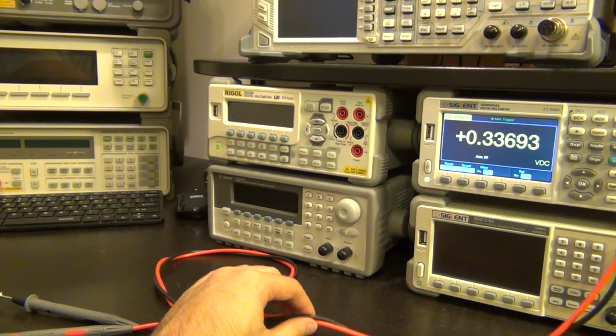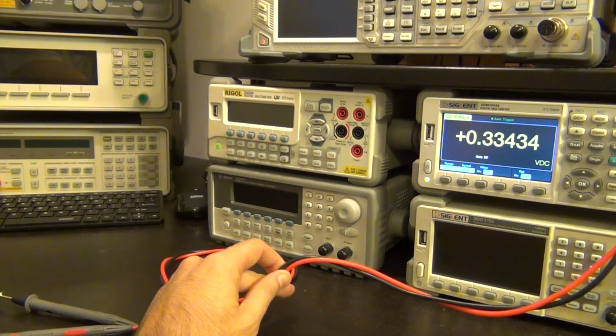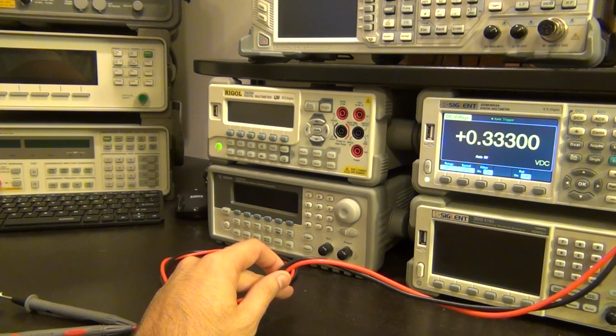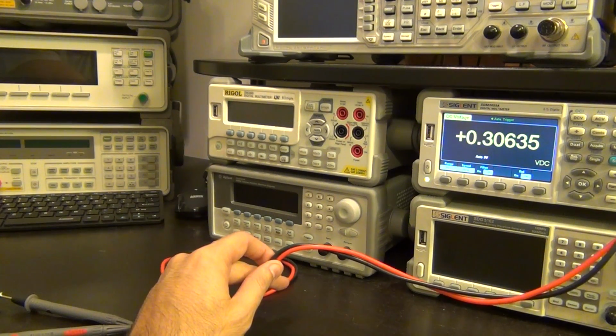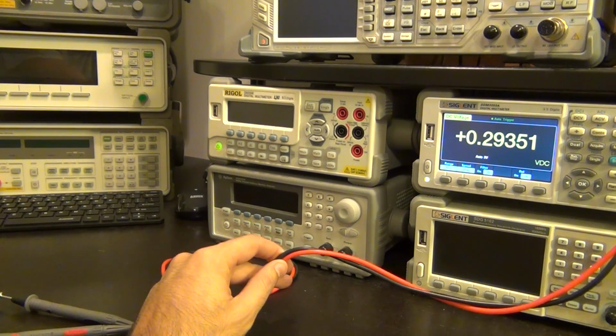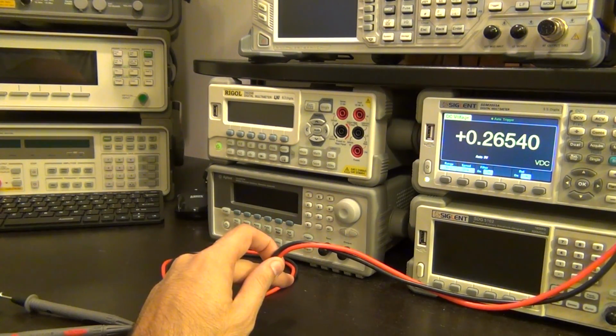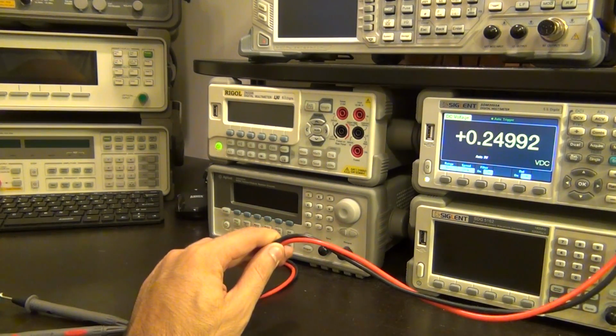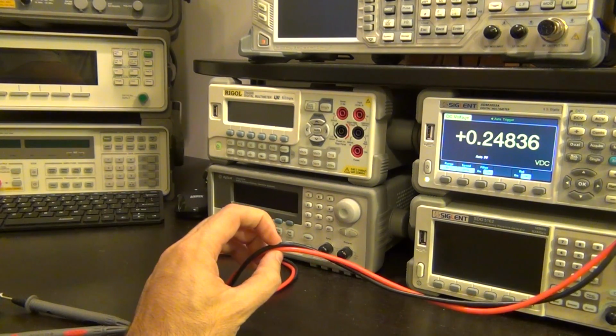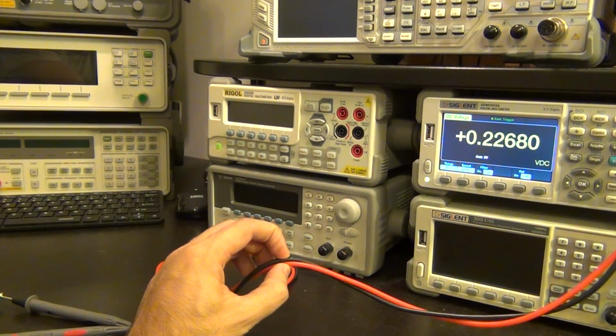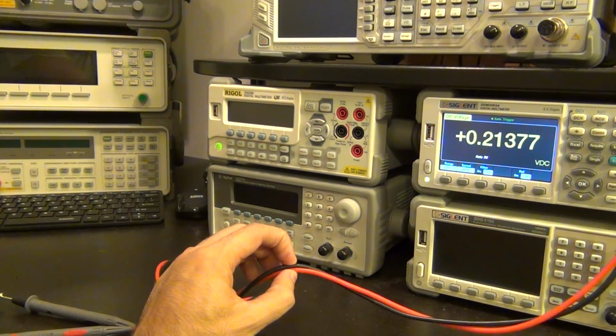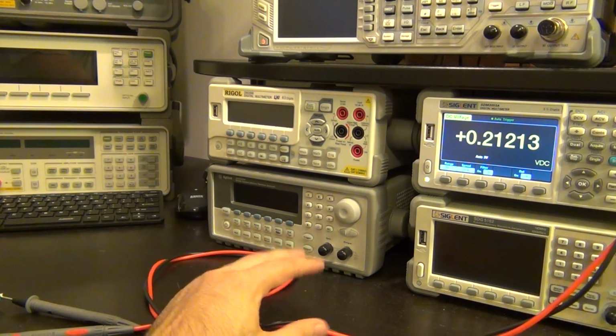Now there's two things I've done. First, I've wrapped the two cables at the input of the instrument together, to make it as easy as possible for the cables to fail at high voltages if they're going to fail. Bringing the two copper centers as close together as possible allows dielectric breakdown to happen at earlier voltages—essentially a stress test on the cables, which we'll do after the first test.